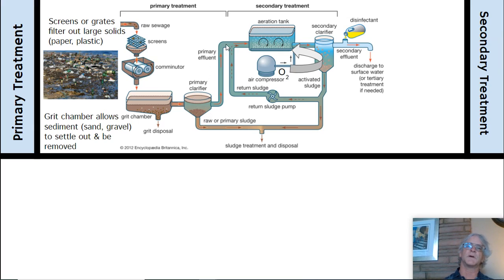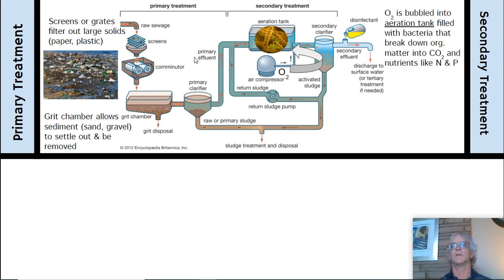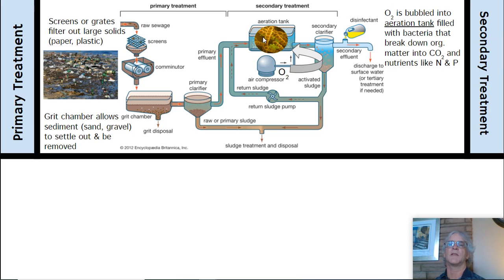The remaining liquid goes up to an aeration tank filled with bacteria, where oxygen is pumped through — because it's an aerobic process — and the bacteria break down organic material into CO2 and nutrients like nitrogen and phosphorus. At Hyperion, they use different bacteria that produce methane instead, and they send that methane directly to an electrical plant next door. Between 40% and 60% of the electricity used by Hyperion wastewater is recovered from that methane.